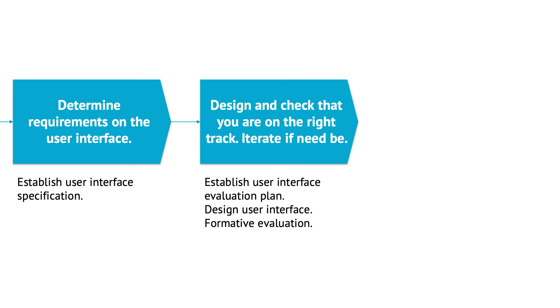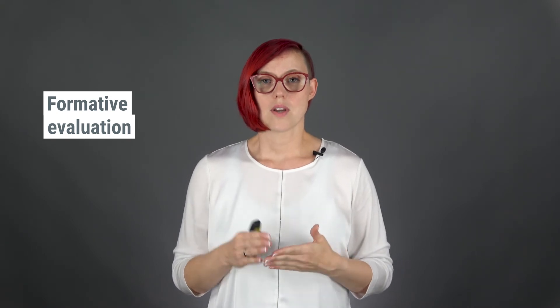Next, you need to implement the requirements by designing the device and its user interface, and check that you are on the right track along the way. That is really important because from experience, you won't get the design right on the first try, especially when designing a new product. There's a term for making tests along the way: formative evaluation. This term is used in usability engineering and also in teaching, where it means almost the same thing — checking that you are on the right track.